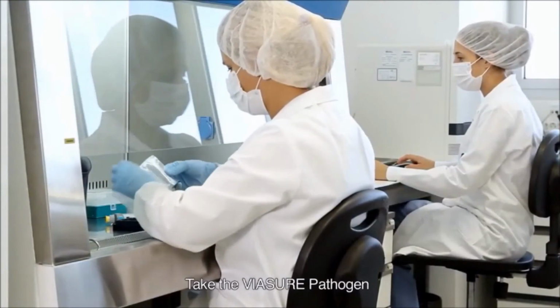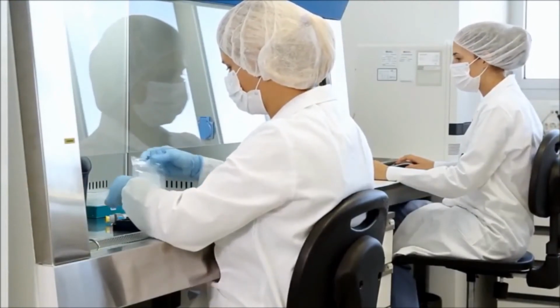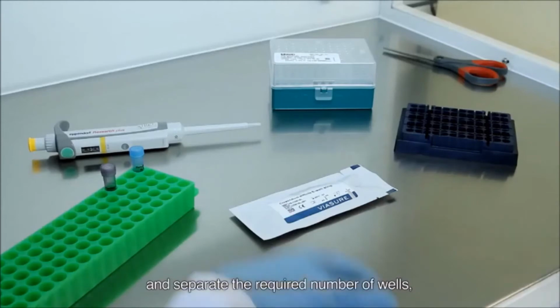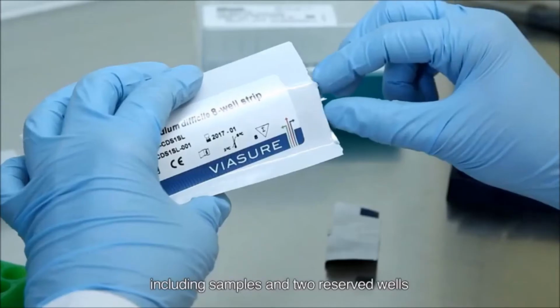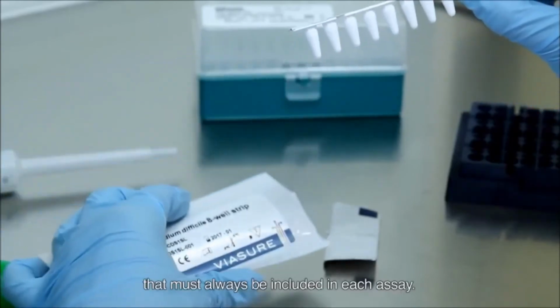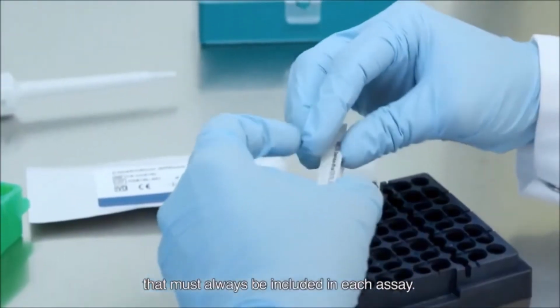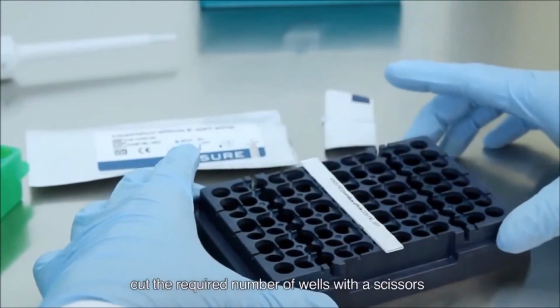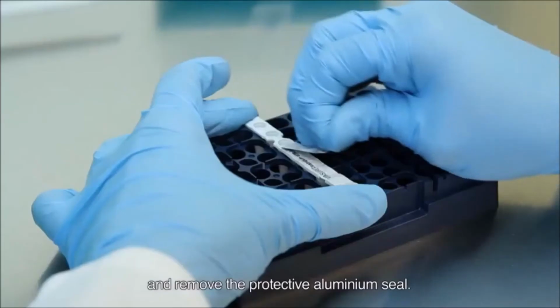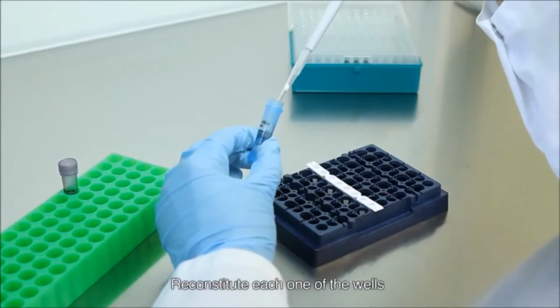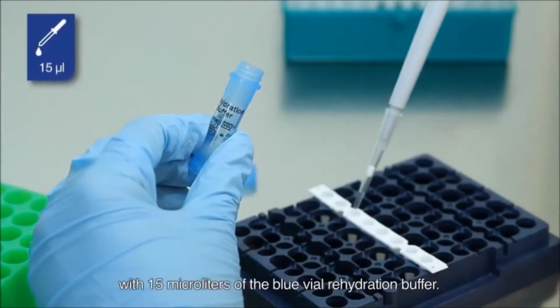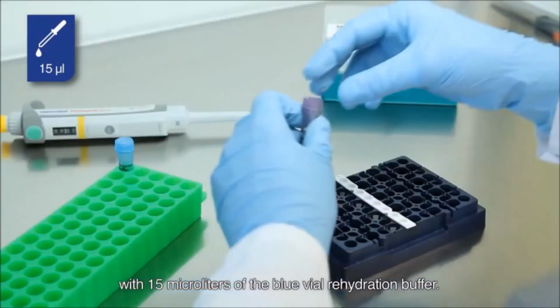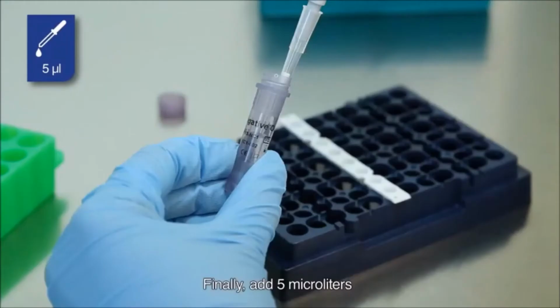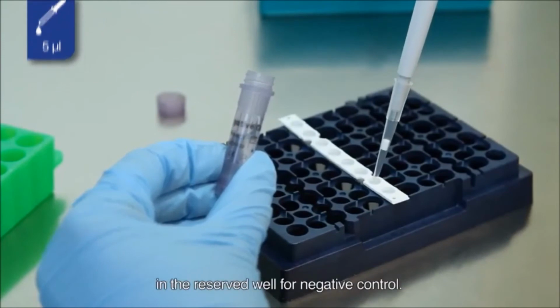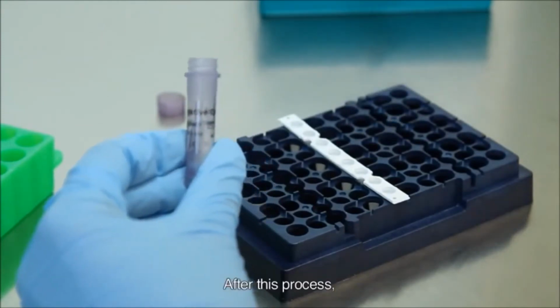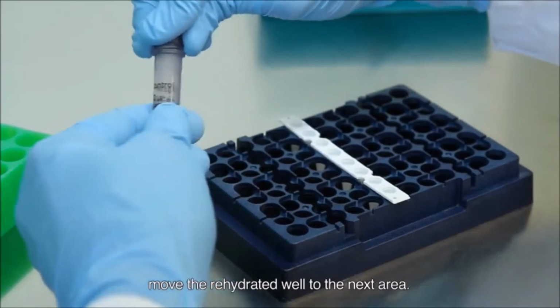Take the ViaSure Pathogen Real-Time PCR Detection Kit and separate the required number of wells, including samples and 2 reserved wells for the positive and negative controls that must always be included in each assay. If necessary, cut the required number of wells with the scissors and remove the protective aluminium seal. Reconstitute each one of the wells with 15 microliters of the blue vial rehydration buffer. Finally, add 5 microliters of the purple vial negative control in the reserved well for negative control. After this process, move the rehydrated wells to the next area.